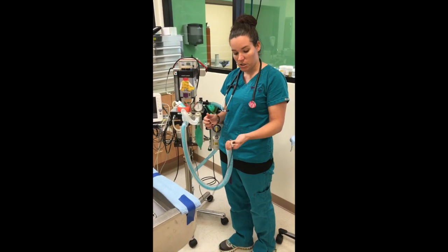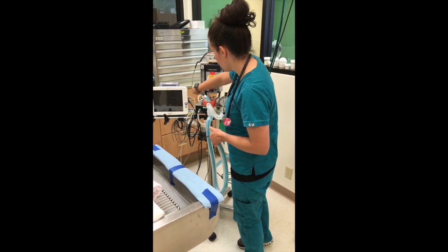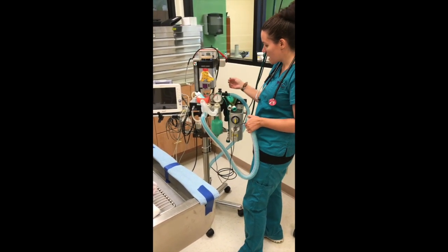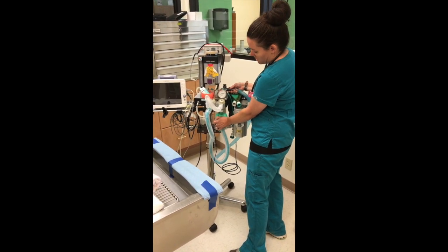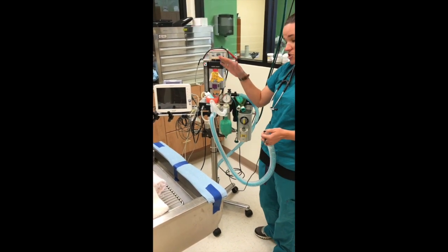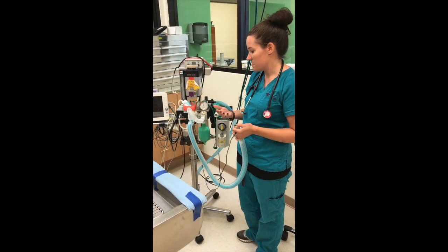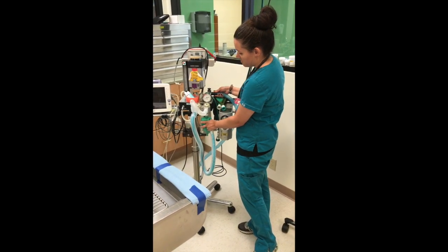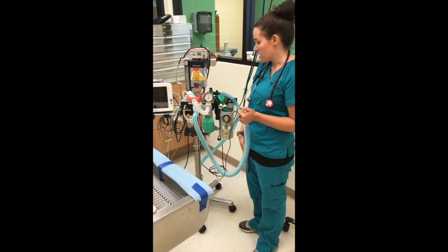I'm going to occlude the end of my tube with my thumb. I'm going to turn on my oxygen, and push this flush button to put a little bit of oxygen into my reservoir bag. I'm going to depress my pop-off valve and squeeze my bag, and I want to make sure that it will hold pressure. If there were a leak in the system that would not hold pressure, that needle would go down, and that would indicate that somewhere in the system there's a leak. Just to do it again, we're going to push up and it's holding without any additional pressure on the bag, so that indicates that the system is sealed, that I don't have any leaks.